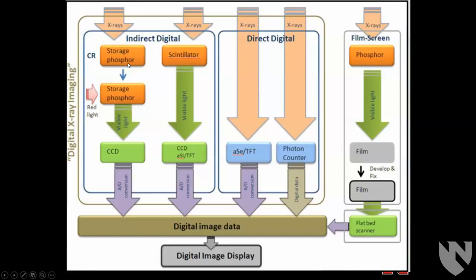In indirect digital x-rays, the x-rays hit a storage phosphor on a sheet that looks similar to an x-ray cassette. You then use red light to release the image from the storage phosphor, which gets detected and turned into a digital image. Or you can have a scintillator that creates visible light going to a digital detector, or have the x-rays directly hit a photon detector that converts them into digital information directly.